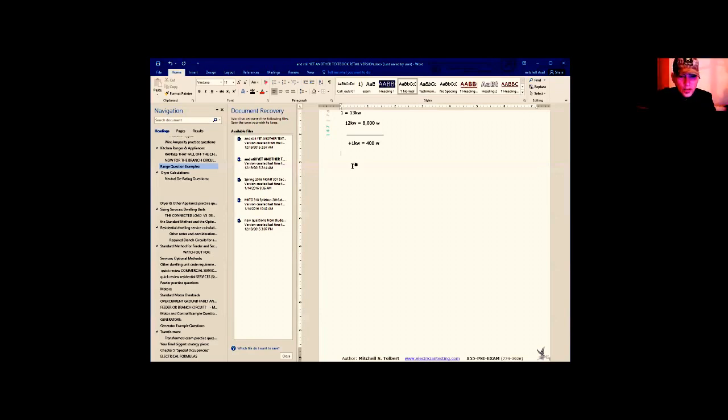All right. So if you've got a range that's equal to 14 kW, what would your number be? 8,800? Yeah, exactly. It's as easy as that. You're just tacking on 400 watts for every kW past the 12. Okay. 17 kW would be what? A single 17 kW range.